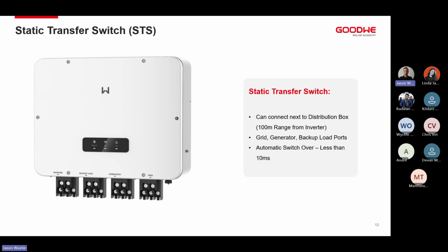Where else can this be useful? In a hospital or hotel environment, you'd install the inverter on the rooftop with the batteries, as close to your DC as possible, and your main incomer might be in the basement of the building with the generator. You can put the STS in the generator room right at the bottom of the building, 100 meters away, 6 floors away, and you only have that one AC cable run.